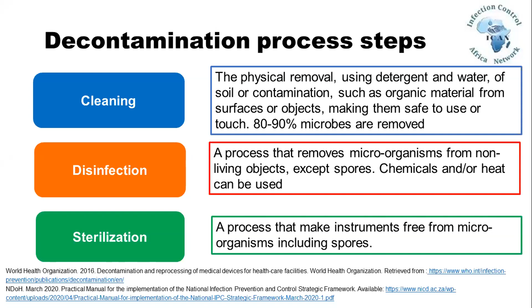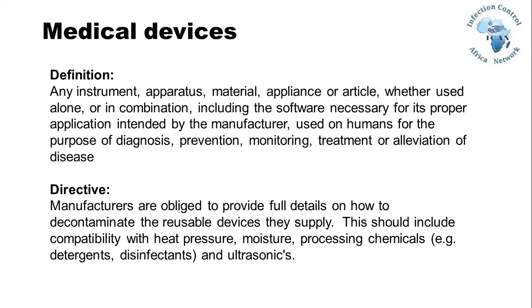It is any instrument, apparatus, material, appliance, or article, whether used alone or in combination, including the software necessary for its proper application intended by the manufacturer, used on humans for the purpose of diagnosis, prevention, monitoring, treatment, or alleviation of disease. So all directives come out through the manufacturers because they are obliged to provide full detail on how to decontaminate the reusable device they supply. This should include compatibility with heat, pressure, moisture, processing chemicals, and ultrasonic baths.